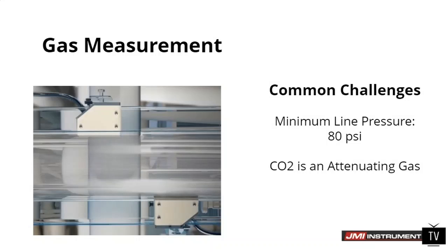Some gases can be attenuating. CO2 is one of those gases. For us to measure CO2, it has to be a relatively high pressure, probably about 4 times the pressure of a normal gas. So in this case, we'd probably look at a line of CO2. We'd probably want somewhere around 300 psi to be able to measure CO2 or have a chance at measuring it.